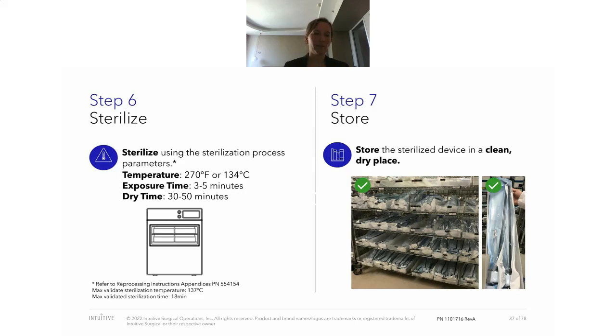And that is dependent on what you have in your facility. And here you can see the general parameters, but we do have, and you see the small print on the bottom, maximum validated temperatures of 137 degrees, and also our maximum validated sterilization time of 18 minutes, which in some jurisdictions is reached. And so we have validated up to those maximum values. And then the next step in our cycle is the storage, and all items should be stored in a clean and dry place. As you can see here, there are different ways of storing instruments, trays, and you all have your own system. These are just some examples.